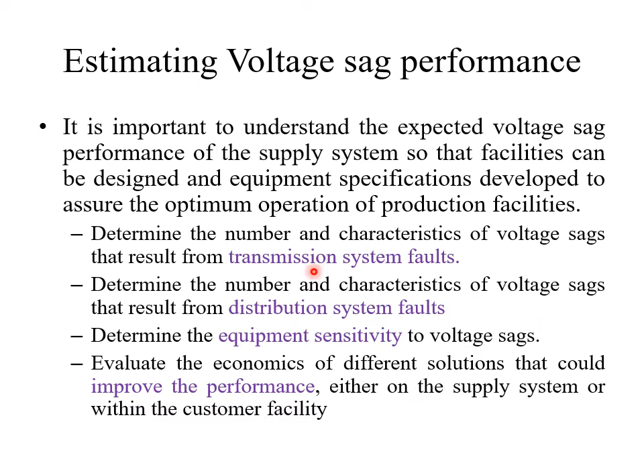You have to determine the number of voltage sags that result from transmission system faults, and then study the characteristics of those voltage sags. The next thing is that you have to determine the number of voltage sags that result from distribution system faults, and then study the characteristics of those voltage sags. And then you have to determine the equipment sensitivity to voltage sag, the equipment that you are using at your level. And finally, you have to evaluate or propose different solutions that could improve the performance of the system, or that will ensure the operation of that equipment.